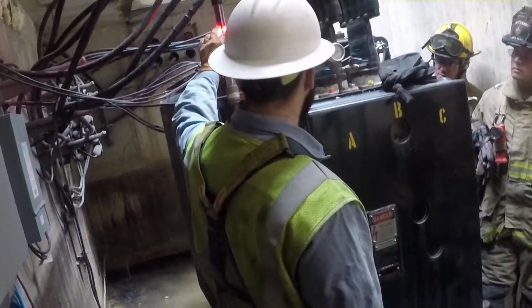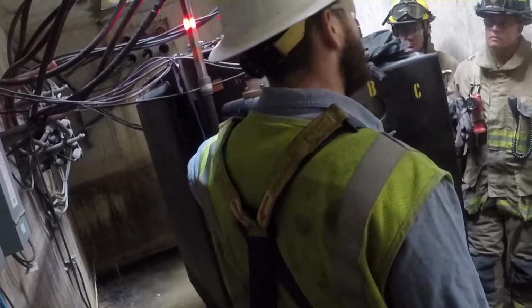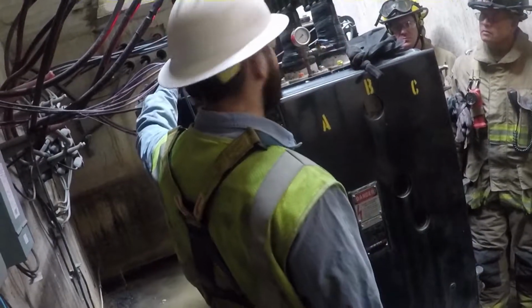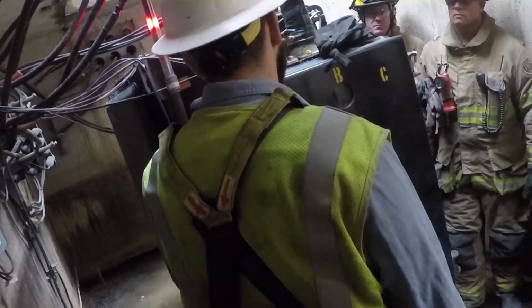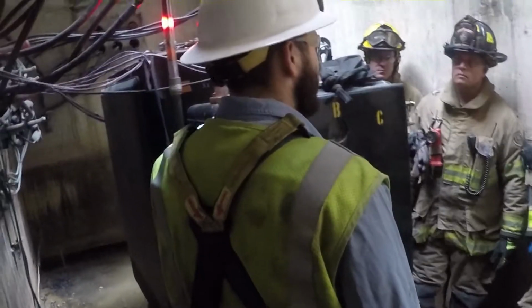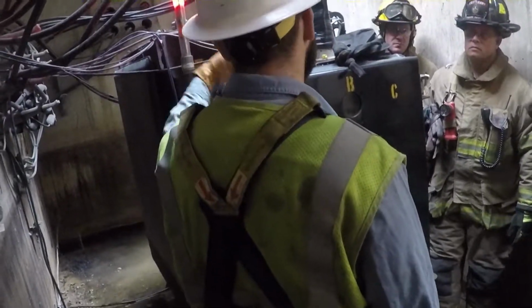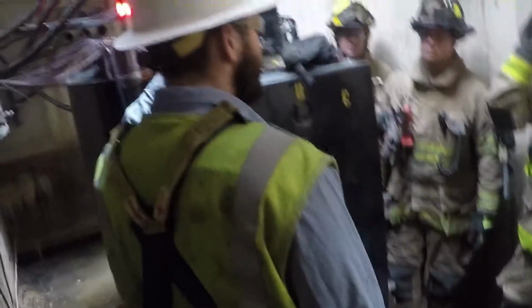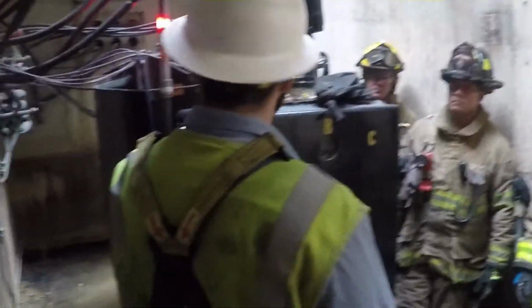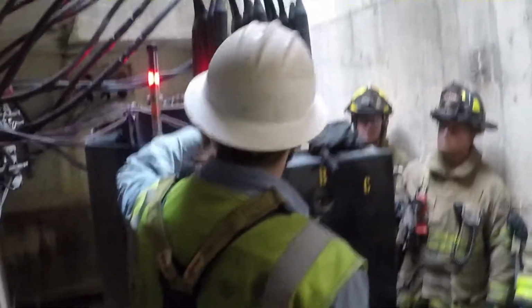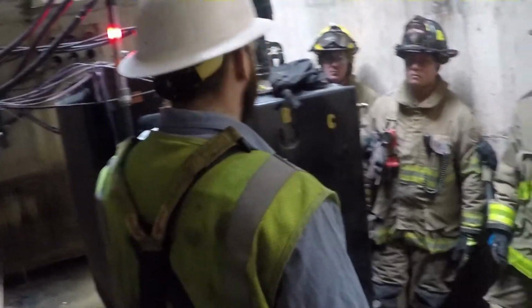What's the red light here? The red signals that this is closed, and if it was open it'd be green. So we just have these on spots, because if both of these would be open, then the building would lose power. So if we're going to be doing maintenance to this, we can look down in here and see this is red, that one's red, so then we're good.